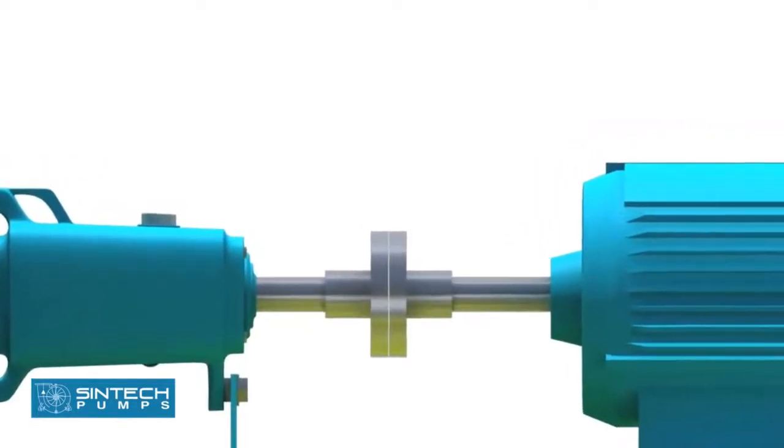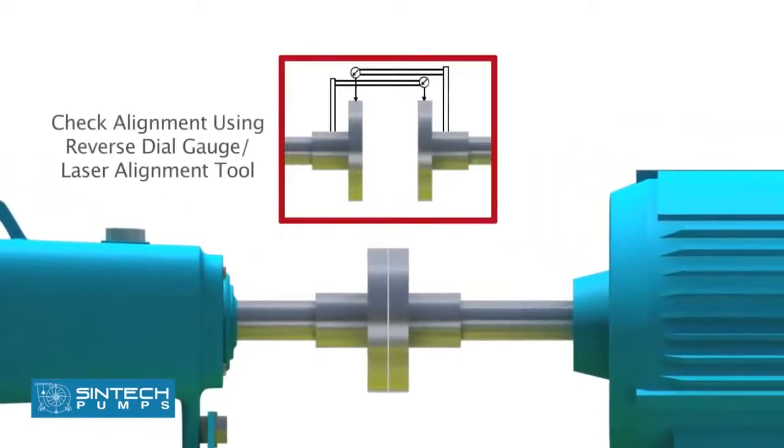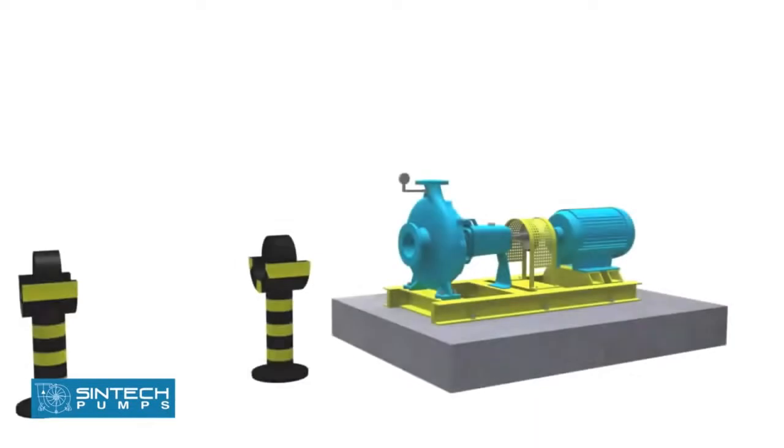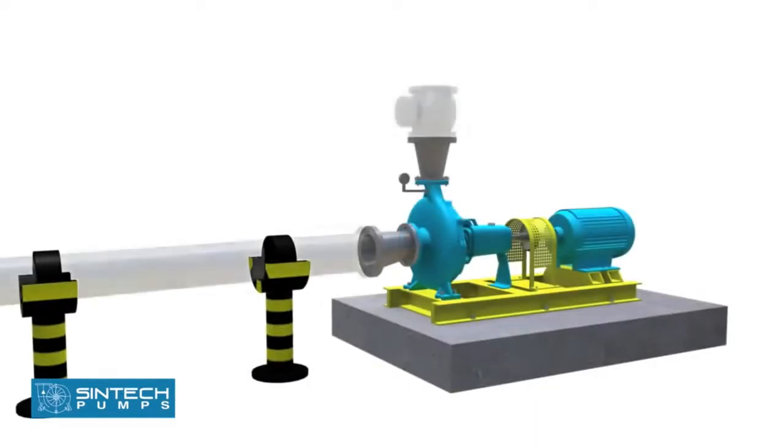In the subsequent step, the pump and the motor are aligned to the final tolerance using a reverse dial gauge or a laser alignment tool. After the alignment is completed, the piping associated with the pump should be bolted.